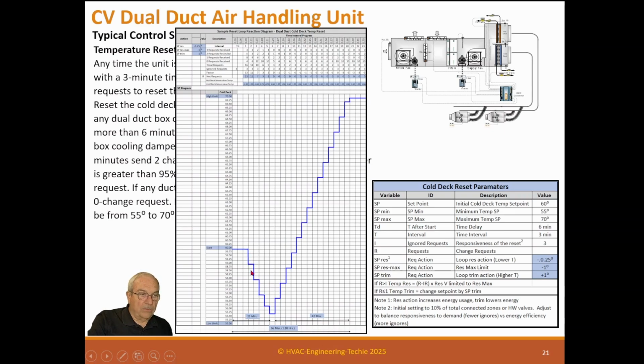An hour, they won't wait that, so it's too long. And then this time here is just information, because this will never happen. You'll never have a condition where you need low, cold air, and then all of a sudden you need really warm air. It would be really weird for that to happen. So normally this goes around and goes up 1 or 2, goes down, goes up. It kind of meanders around in real life. But I'm setting this up to prove what these maximum times are.